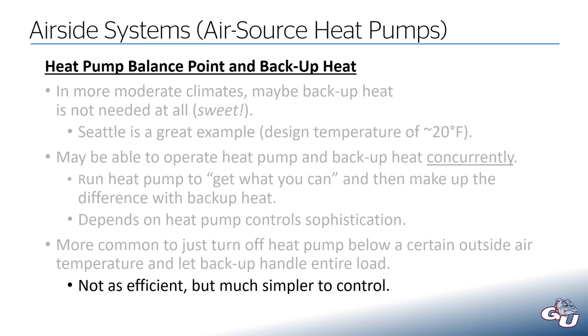You might operate your heat pumps and backup heaters simultaneously — run the heat pump to get what you can out of it, maybe serving half the load, then only turn on backup heat to make up the difference. That takes more control sophistication. It's more common to just say: below some outside air temperature, turn on the backup heat and let it run — turn off the heat pump completely and let the backup heat do everything. That's less efficient but simpler in terms of control: just wire an outside air temperature sensor, and if it sees below say 15 degrees, lock out the heat pump and only run the backup heat.